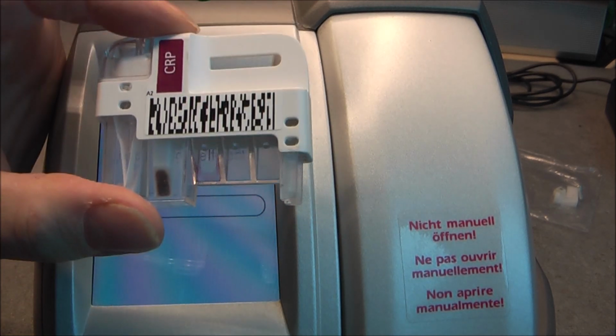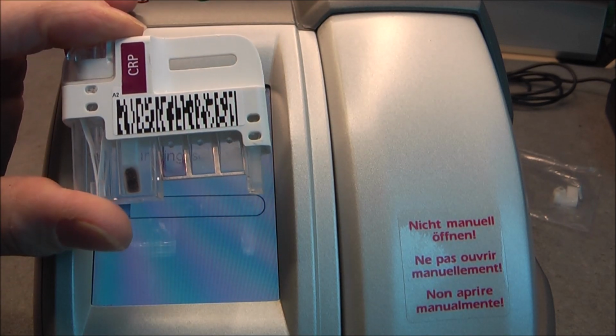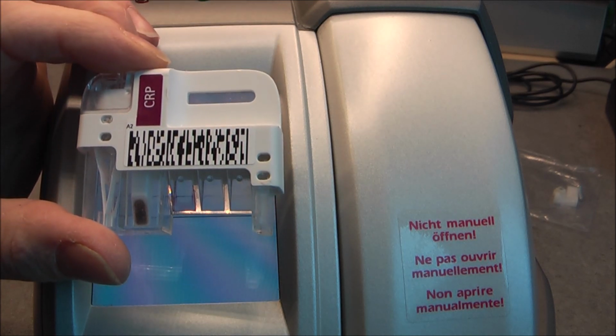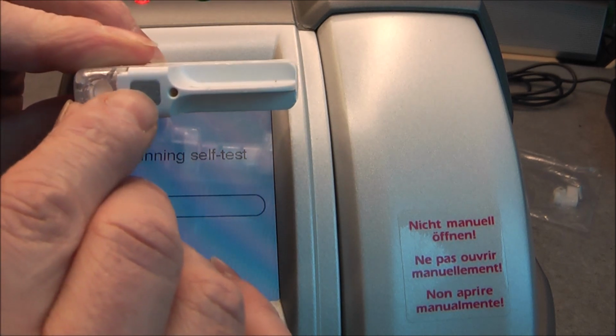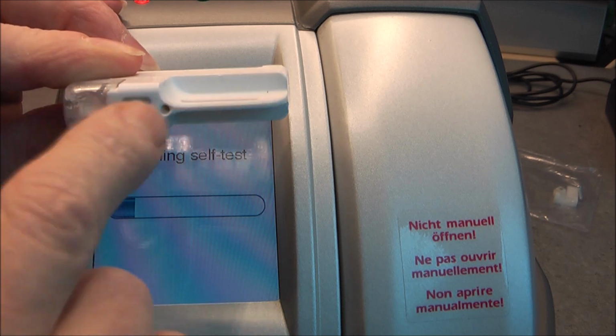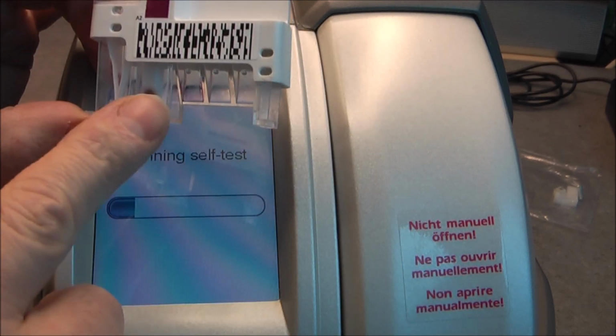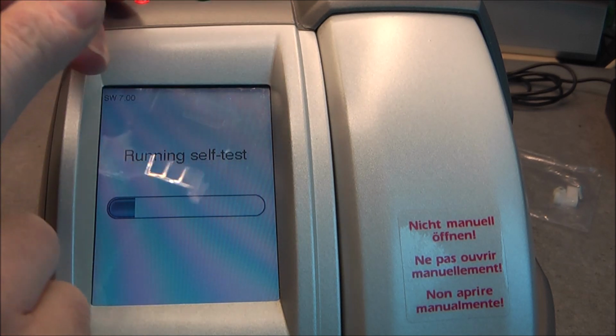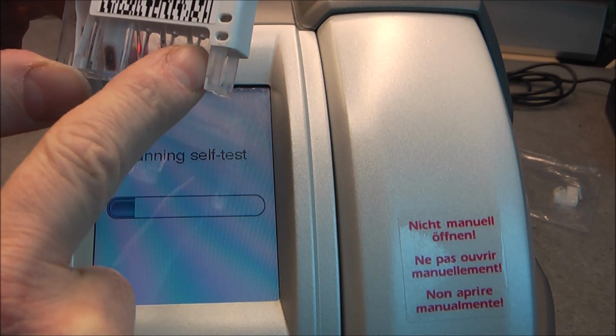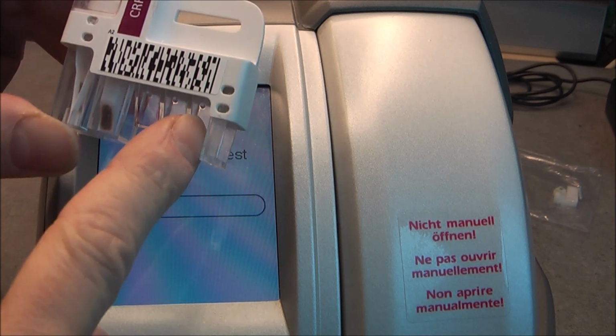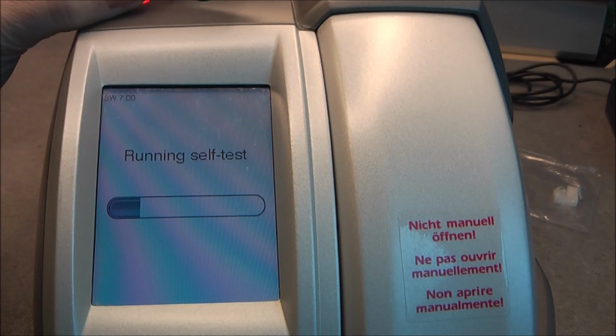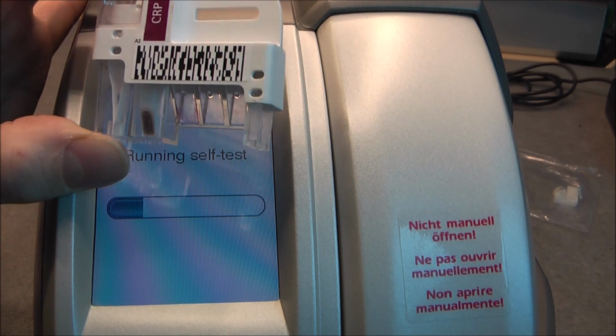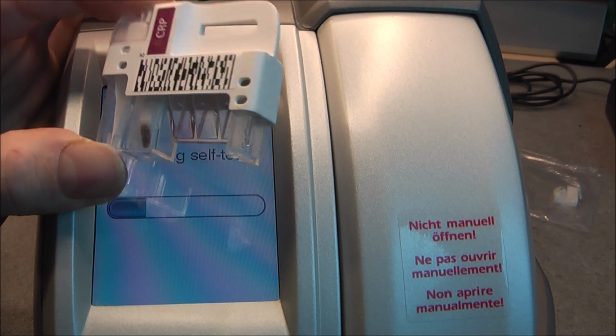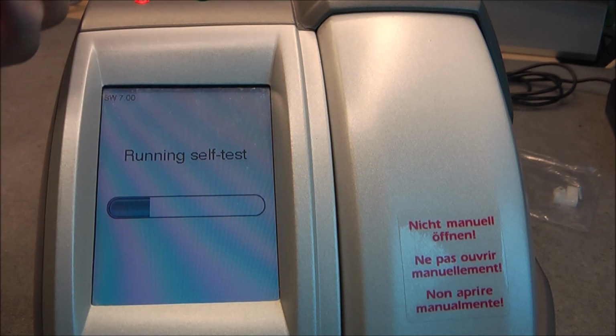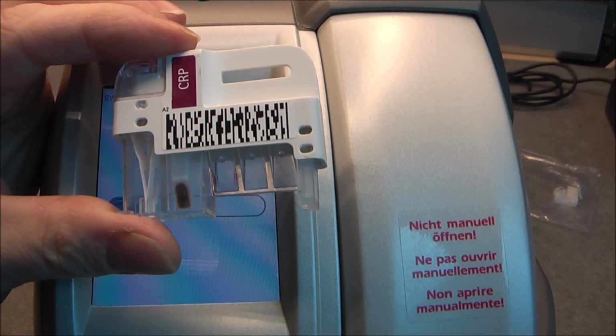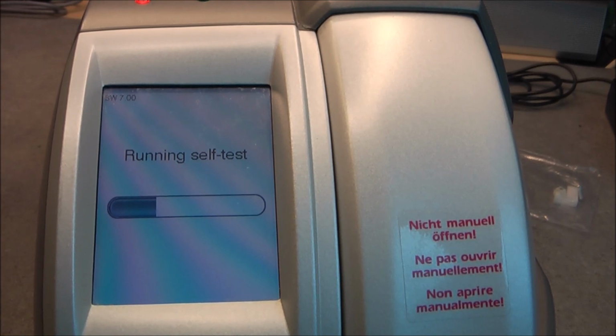When you load the cartridge into the device, it will first read this number. It will test if the cartridge is valid. Then it will activate it, I believe, by poking a needle through this rubber part here. It will blow air in the cartridge. It will mix the sample of blood and the reagent, and somehow some of the reagent and blood mix will go in these three parts here, and a camera inside the device will read the results thanks to a calibrated color light source also. And the camera at the same time is responsible for checking if the cartridge is processing normally. That is the information I found in the user manual.